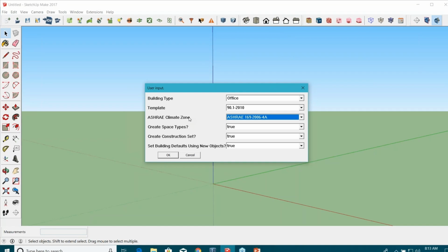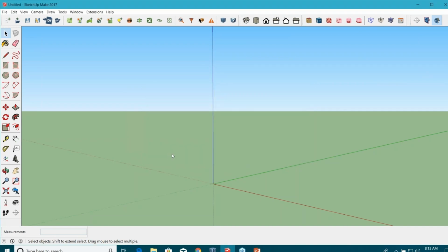Envelope is based on the climate zone, while properties such as internal gains and lighting power density are related to the building type. For example, for an office building, the lighting power density is somewhere around 0.98 watt per square foot for ASHRAE 90.1 2010 compliance. It is not dependent on climate zone, okay? But still, we need to provide all these properties.